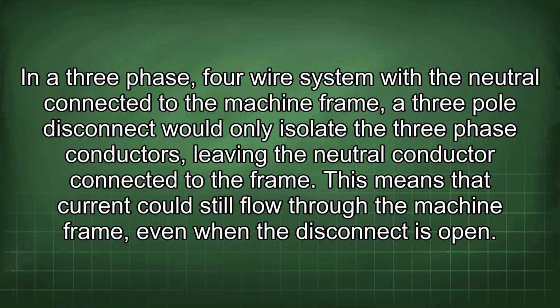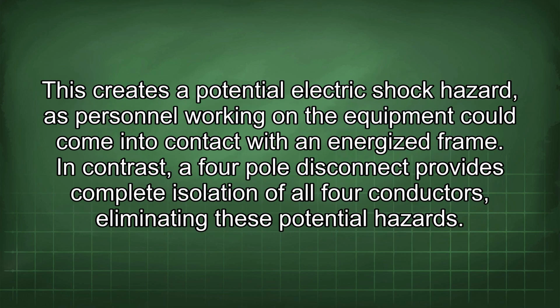In a 3-phase, 4-wire system with the neutral connected to the machine frame, a 3-pole disconnect would only isolate the 3-phase conductors, leaving the neutral conductor connected to the frame. This means that current could still flow through the machine frame, even when the disconnect is open. This creates a potential electric shock hazard, as personnel working on the equipment could come into contact with an energized frame. In contrast, a 4-pole disconnect provides complete isolation of all 4 conductors, eliminating these potential hazards.